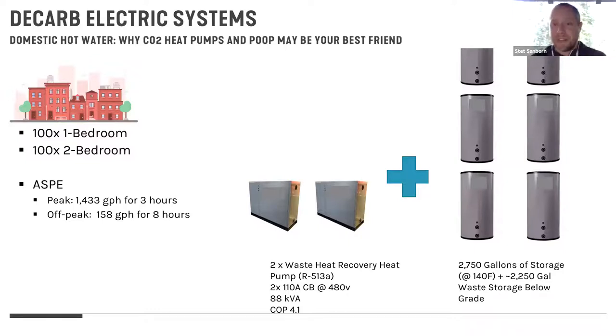Now the downside with one of these systems is you still need all that hot water storage. It only makes 140 degree water. And you also need the below grade or parking garage grade sewage storage, which tends to be between 1500 and 2500 gallons of sewage storage on site, which has an ick factor. You have to get over that with your clients. But this is an example of finding the appropriate source of energy to both increase your performance, you get a COP of 4, and also reduce your connected load, which is going to bring down the electrical cost on that same system.